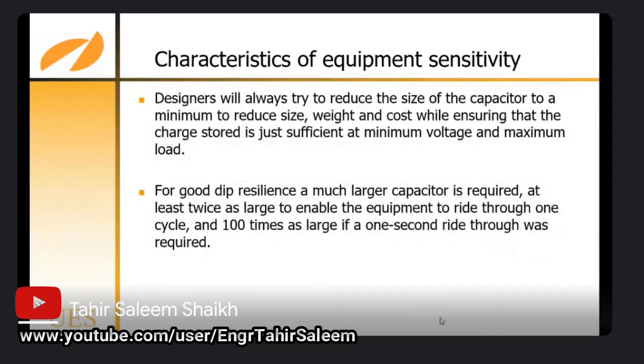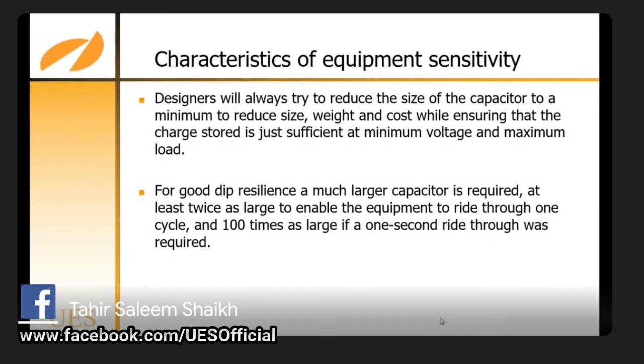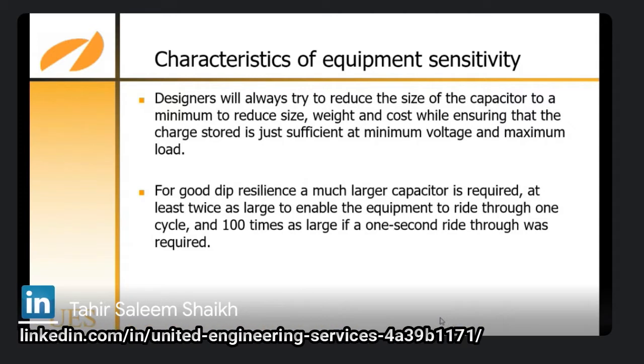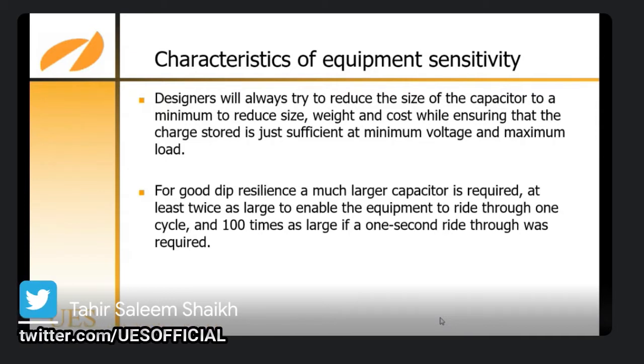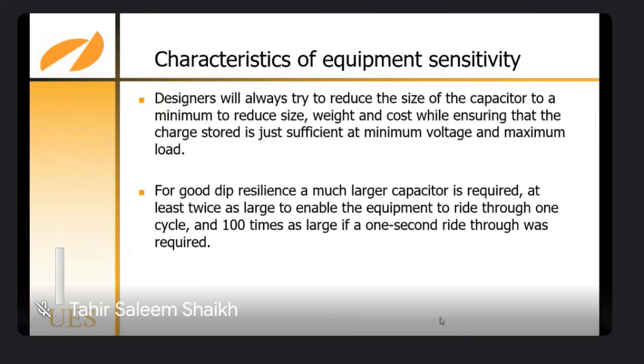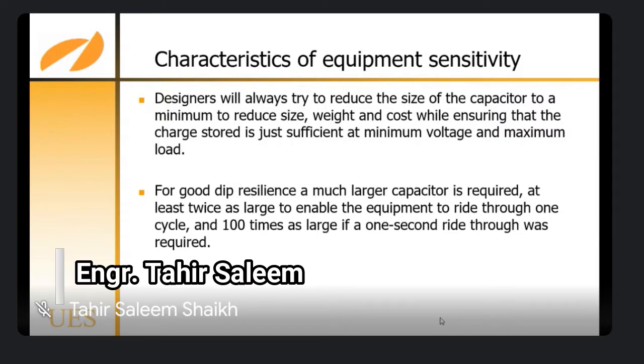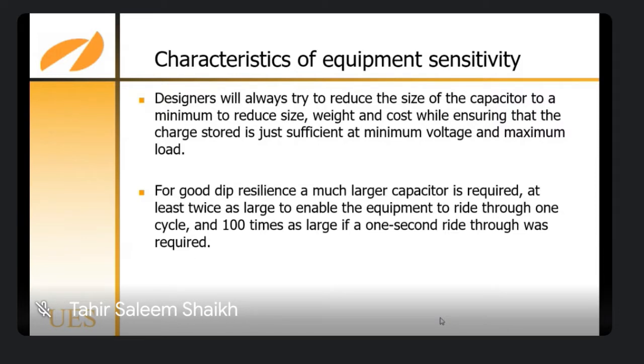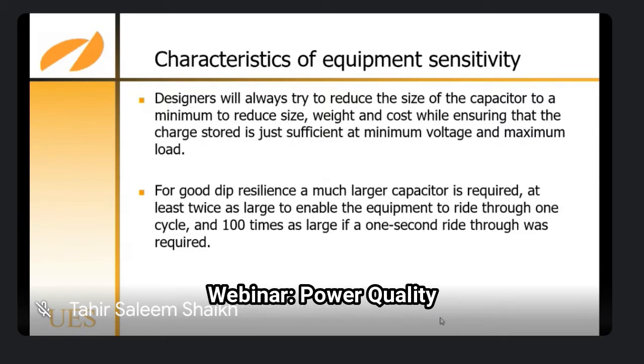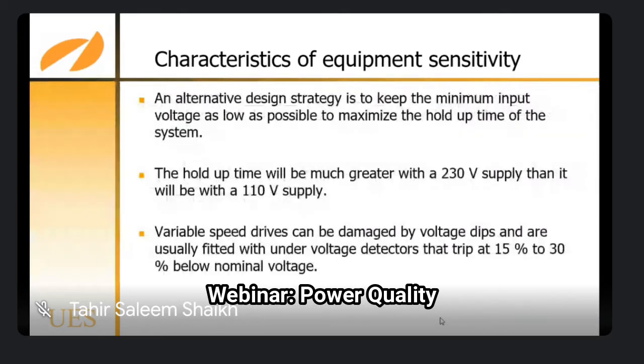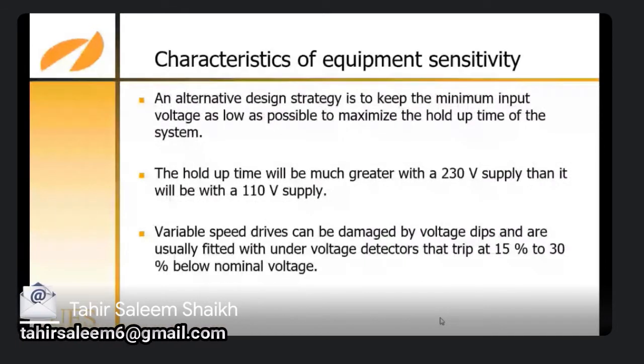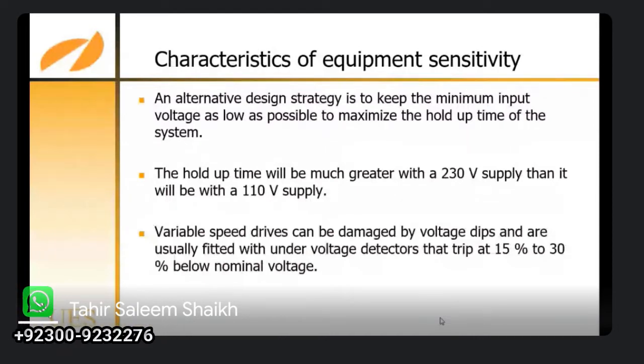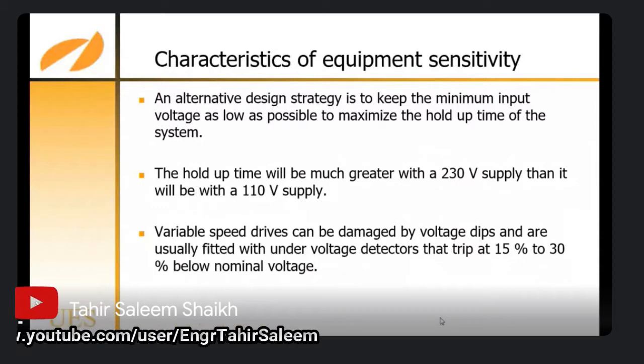Designers will always try to reduce the size of the capacitor to a minimum to reduce size, weight and cost, while ensuring that the charge stored is just sufficient at minimum voltage and maximum load. For good dip resilience, a much larger capacitor is required, at least twice as large to enable the equipment to ride through one cycle, and 100 times as large if a 1 second ride through is required. An alternative design strategy is to keep the minimum input voltage as low as possible to maximize the hold up time of the system. The hold up time will be much greater with a 230 volt supply than with an American 110 volt supply.